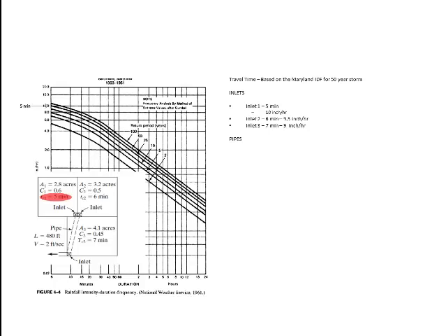Pipe 1 refers to the pipe after area A1 and A2 are combined. We compare the travel times in area A1 and A2. In order to calculate the governing intensity, we pick the longest travel time, which in this case would be for area 2, or 6 minutes. Thus, we will use 9.5 inches per hour when we calculate the flow rates for Pipe 1.